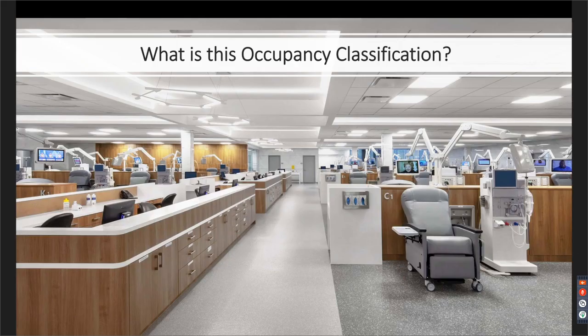So with that in mind, in this particular infusion center, what occupancy classification would this be? Well, these patients by definition are incapable of unassisted self-preservation. It looks like there's more than 5 stations. So this would be an I-2.1 occupancy. Is it OSHPD 3 or not? That's not material at this point. Right now, we're just defining the occupancy, and it's important to realize OSHPD 3 could be a B occupancy, or I-2.1 could be a non-OSHPD 3 facility. The two are not related to one another. Occupancy classification is based on the patient and the number of patients, and OSHPD 3 requirements are based on whether the facility is licensed or not.